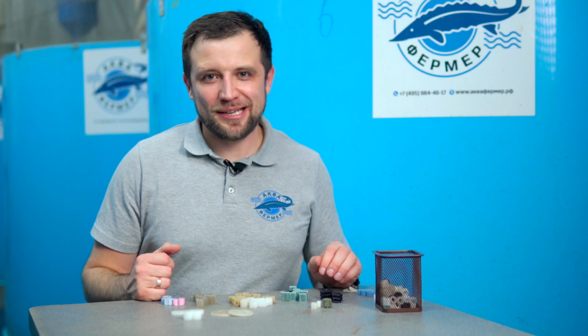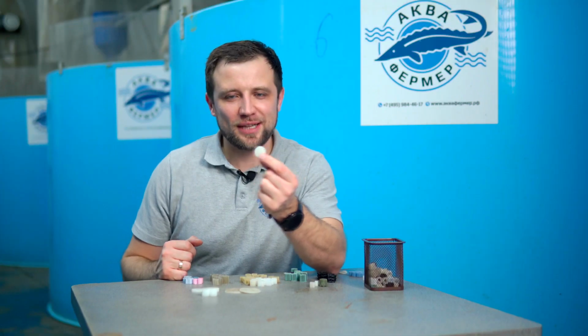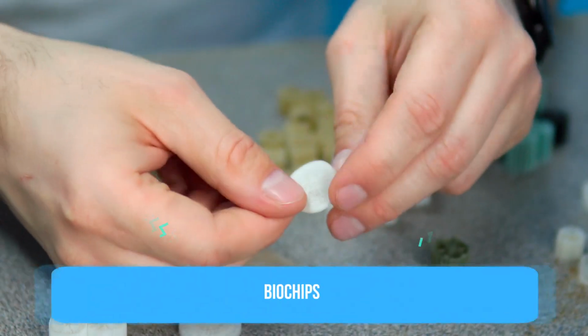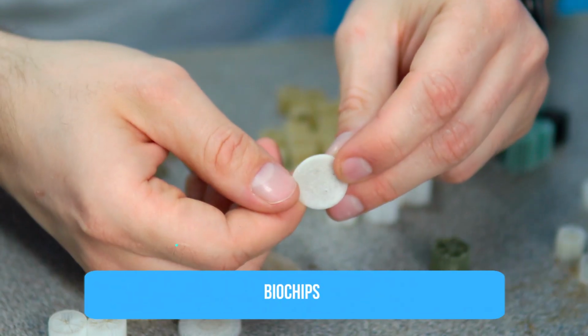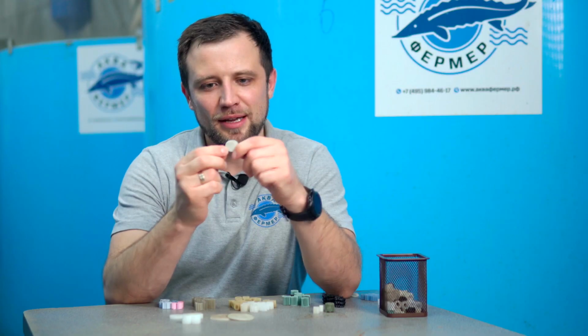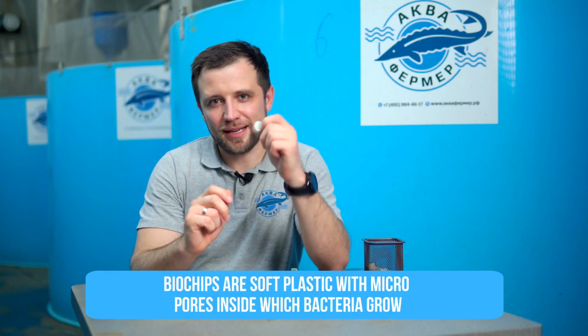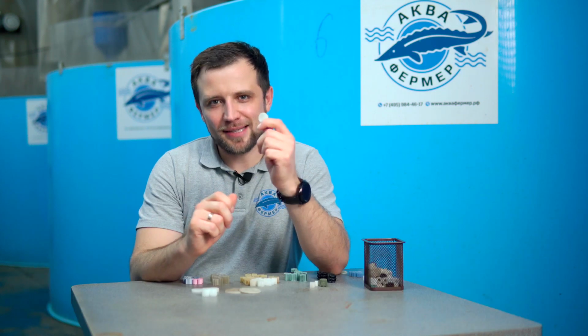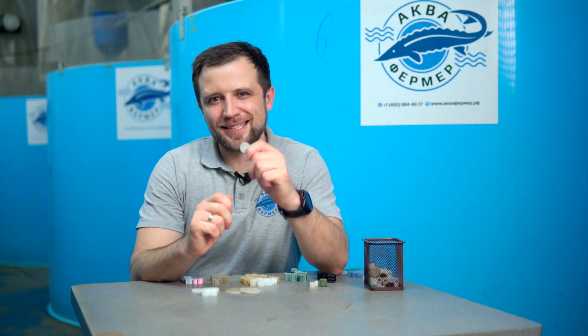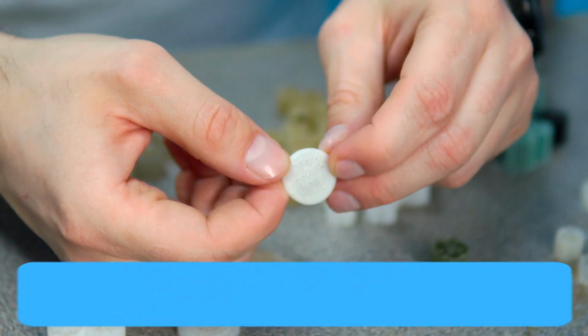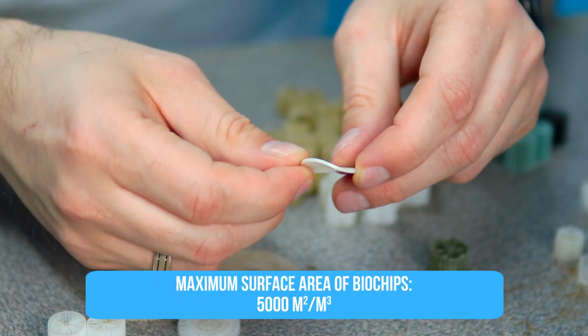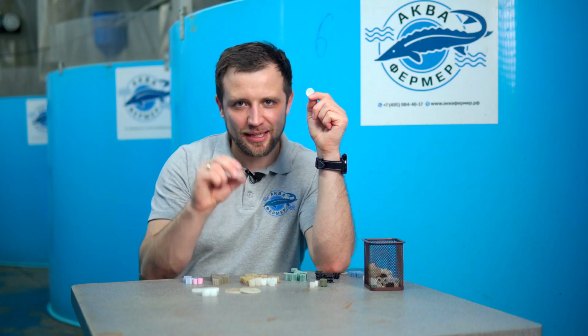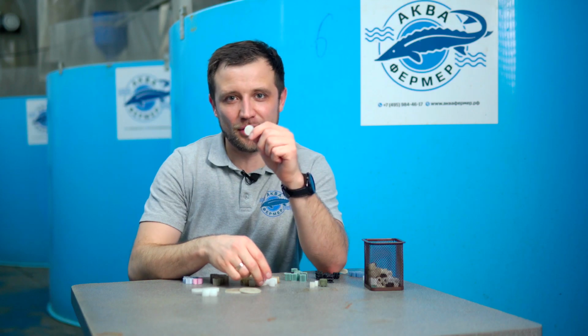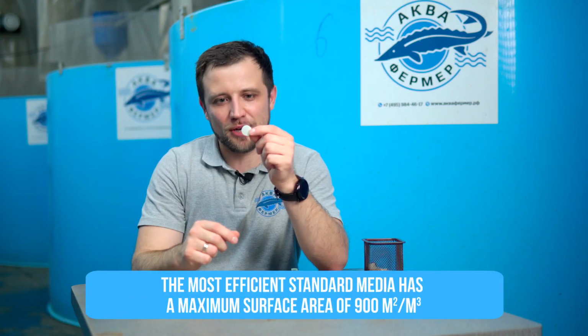And now let's talk about the latest achievements in media manufacturing. This one is called biochips. There are several companies producing it right now, primarily in Europe. It's a soft plastic with micropores, inside which bacteria are growing. This media can have a surface area of up to 5,000 square meters per cubic meter, whereas the most efficient of the conventionally standard media has a maximum surface area of 900 square meters per cubic meter, which is 5 times more.